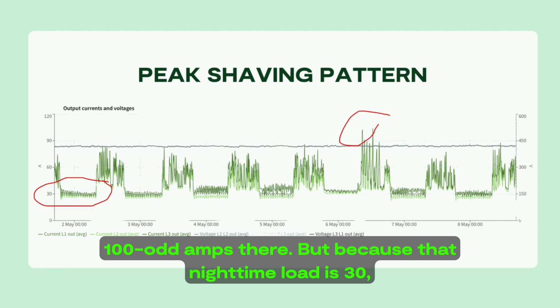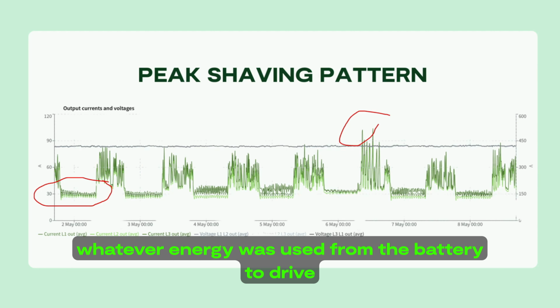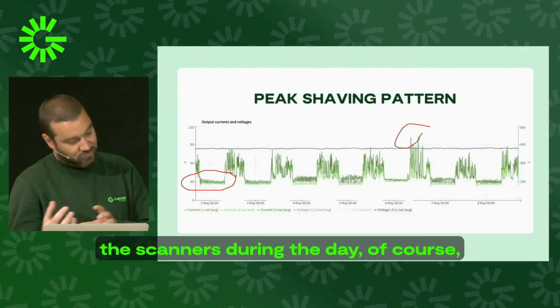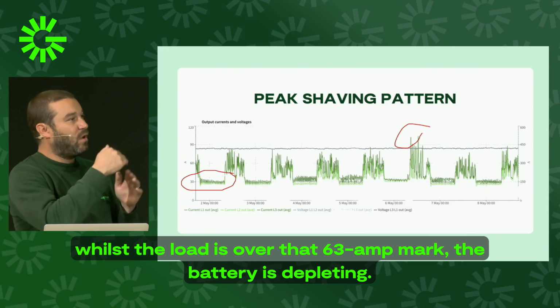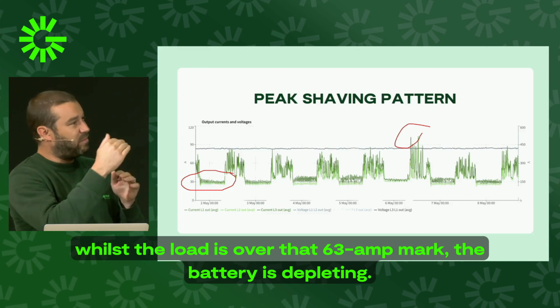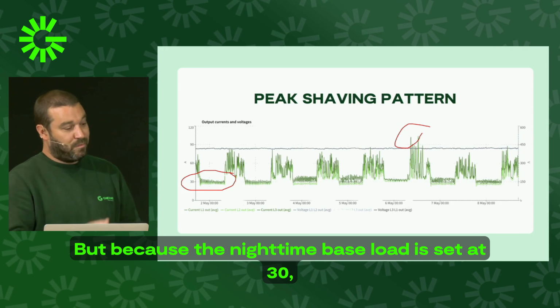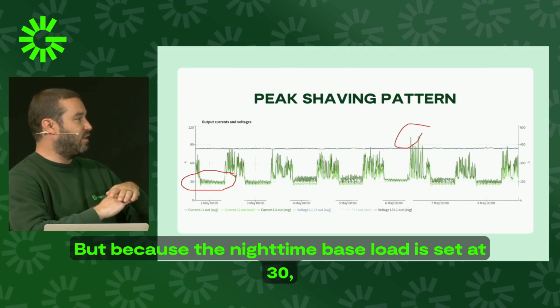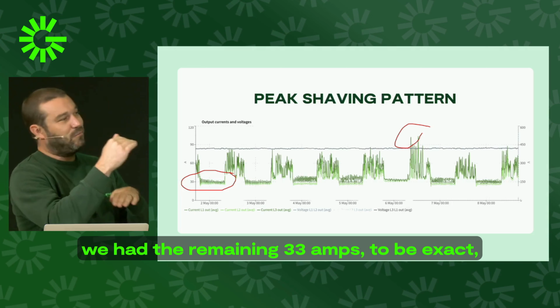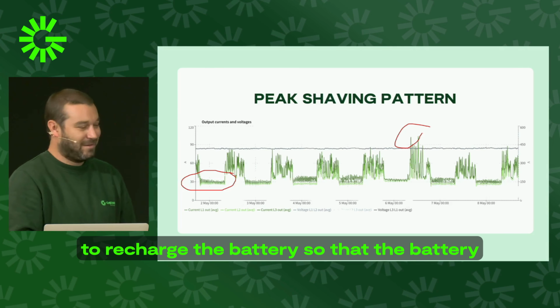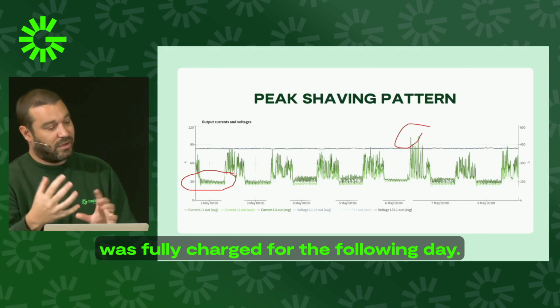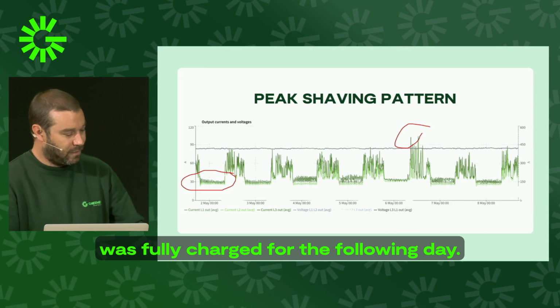But because that nighttime load is 30, whatever energy was used from the battery to drive the scanners during the day, of course, whilst the load is over that 63 amp mark, the battery is depleting. But because the nighttime base load is 30, we had the remaining 33 amps to recharge the battery so that the battery was fully charged for the following day.